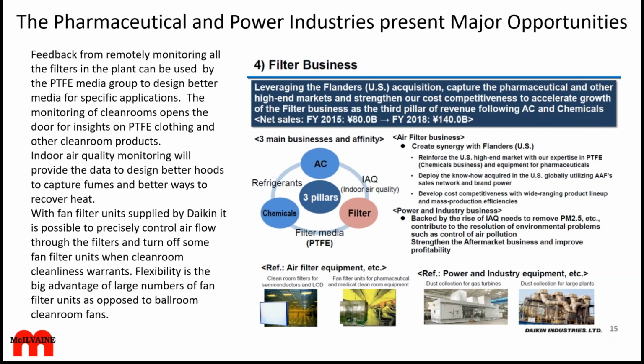But it was found that if you have a little 1,000 CFM filter with a fan over every 2x4 filter unit, which they then call a fan filter unit as a combination, you can control every 2x4 section of your ceiling through one fan. They've gotten the price of those down to where it's not a whole lot more money to put in 1,000 fan filter units than one big fan with the filtration system.